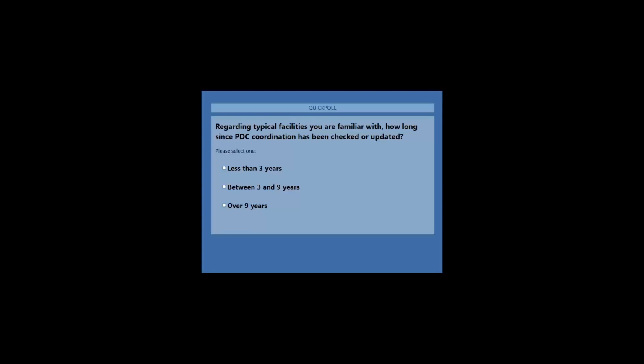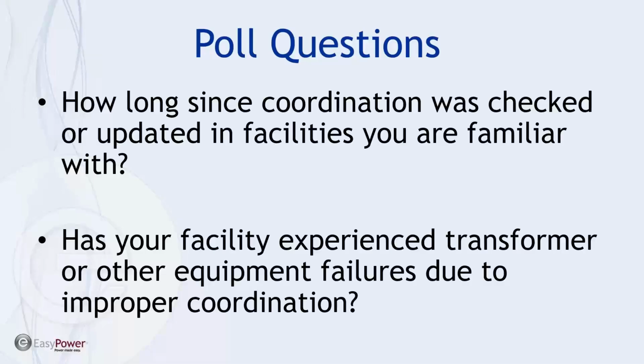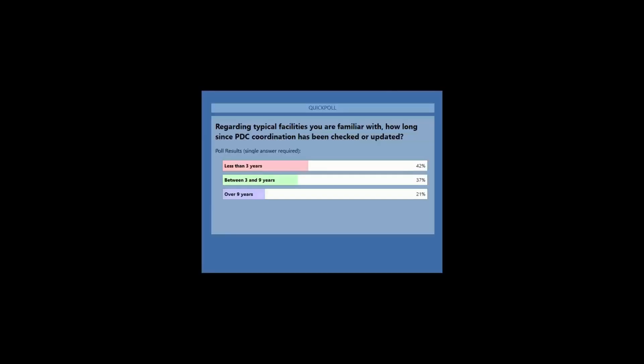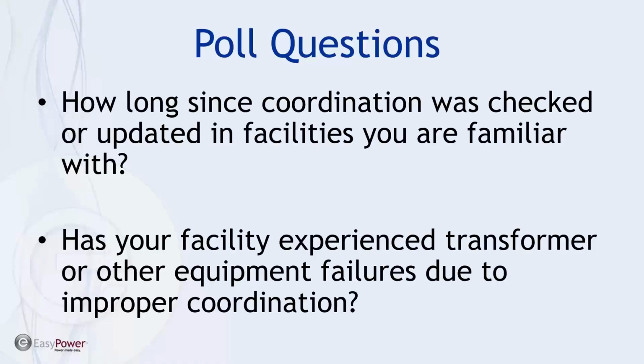All right, let's leave this about another 5 seconds. Looks like we're close to a quorum. All right, here's how folks have responded. It's a pretty wide distribution. Now, theoretically, you don't have to do a coordination study that often because it's part of the initial commissioning of the building and the equipment. But if there's any chance that anything was changed, or that loads have changed, or that anyone has replaced fuses, there's a need to potentially see if anything has been modified.